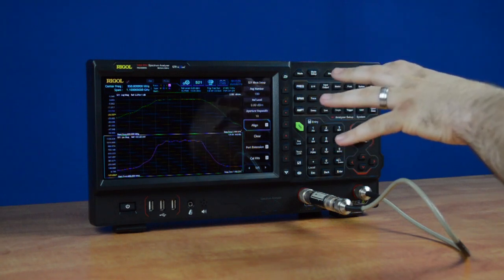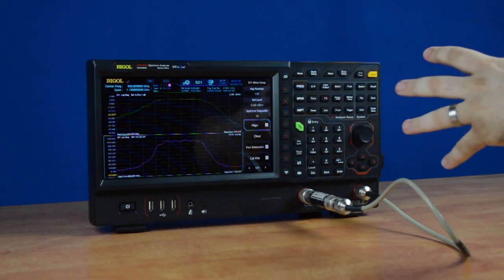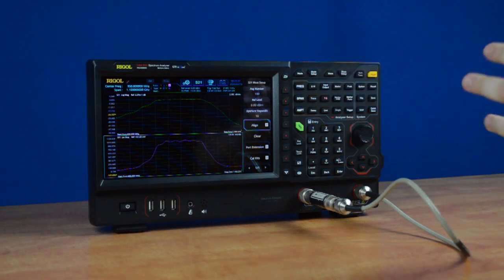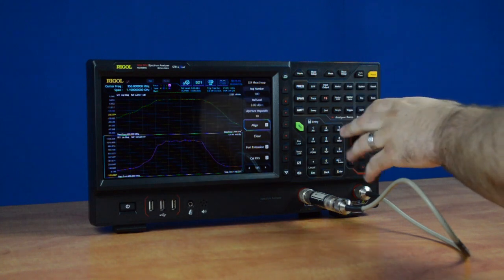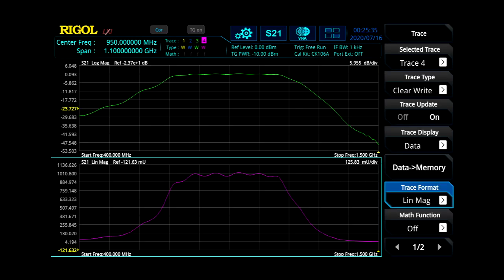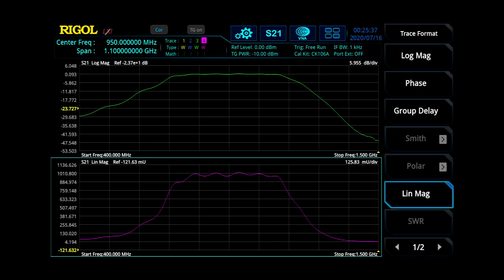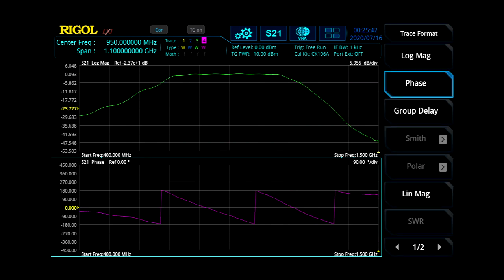There are a couple of things we can do within S21 measurements to take more precise measurements. First, we can go into the trace menu and change our view to either phase, group delay, lin mag, or log mag view.